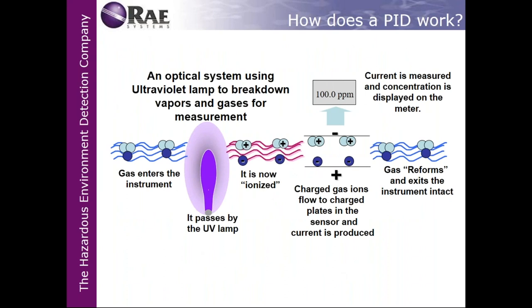So in this picture, you're going to see gas enters inside the instrument and it passes by the UV lamp. When it becomes ionized, you'll notice that it gets separated. In the real world, what I usually tell people is there's like a little mini explosion or a poof that happens. So as the particles ionize, you'll have that electric current that shows up as charged gas ions, and then it is measured by the monitor itself, just that electric current, and then when it leaves the chamber, it comes back together.